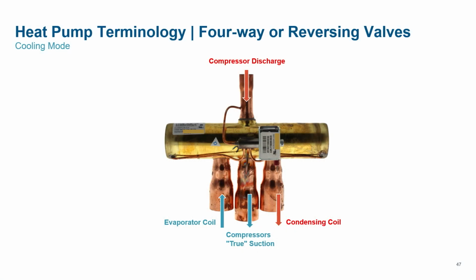Another common component is the four-way or reversing valve. This is a mechanical switching device that redirects the discharge gas in the proper direction to either heat or cool the space. In the cooling mode, the gas is directed to the outdoor condensing coil before making its way to the evaporator. In the heating mode, the gas is directed to the indoor coil before making its way to the outdoor coil. With heat pumps, outdoor coil frosting is a perfectly normal occurrence. The outdoor coil typically operates between 15 to 20 degrees cooler than ambient temperatures. This operating range is dependent on the refrigerant type and density. For that reason, the rate of frost accumulation depends on the ambient conditions.